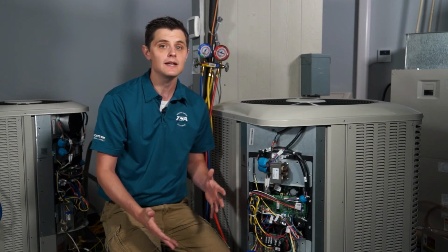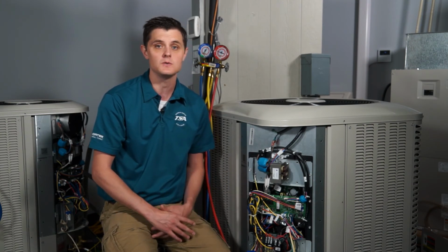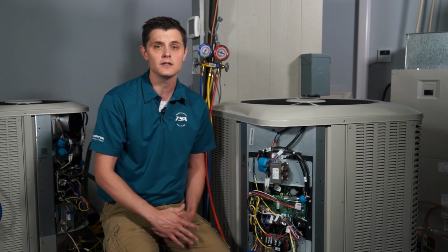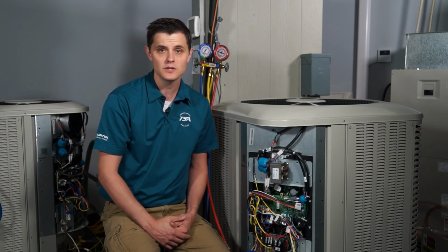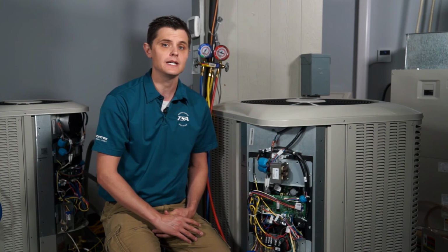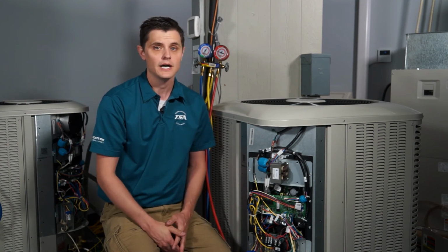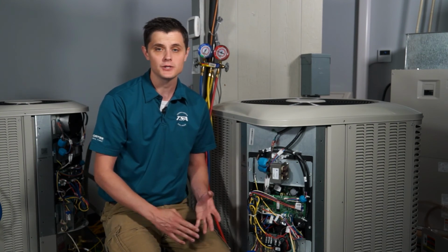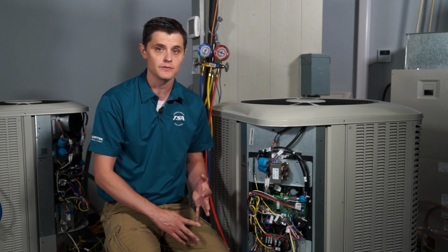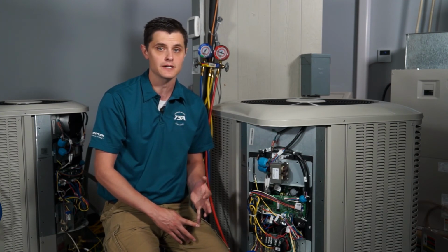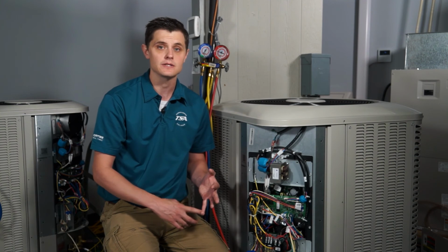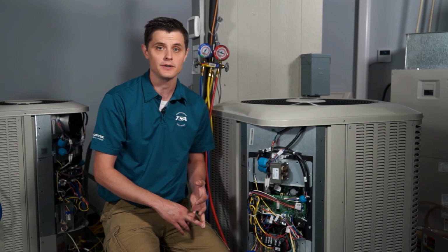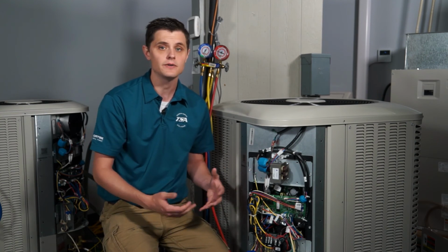Now, what you may get as a result for some codes is you may see an active 14 code and an active 18 code. You may even see an active 02 code. Those codes kind of relate to power in the compressor. Mainly like if you were to pull the disconnect in the middle of a run cycle, you're for sure going to get your 18, which is your condenser fan motor fault, because that goes directly off your contactor. You're taking power away, so it's going to think the condenser fan motor is bad. And then also, it's going to take away power from your inverter, and it's also then going to think that your inverter is bad.